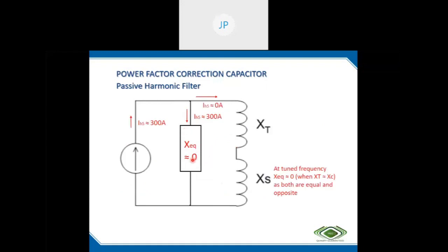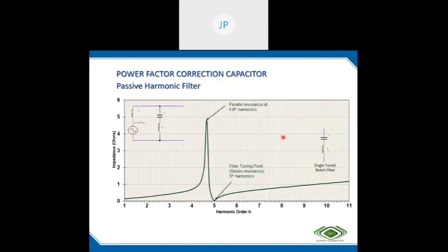Xeq at the fifth harmonic is zero. The entire current will flow through this one. Negligibly small current will flow through this one, and no harmonic injection. This is the frequency scan diagram of impedance. So the tuned reactor will be tuned somewhere here. We are tuning exactly here. The impedance is zero.